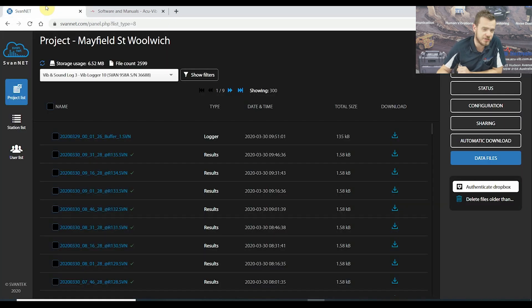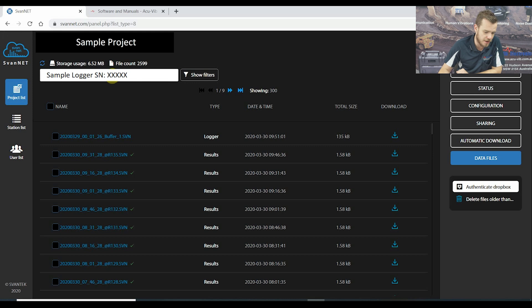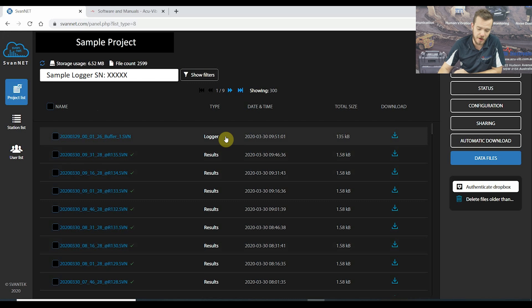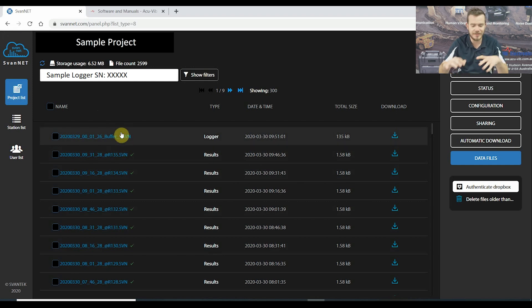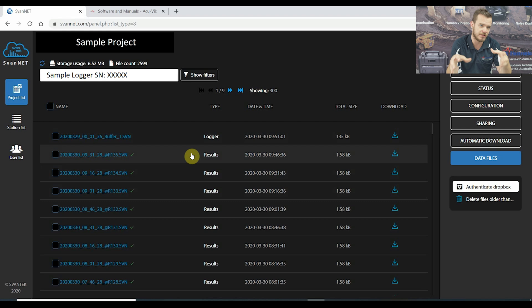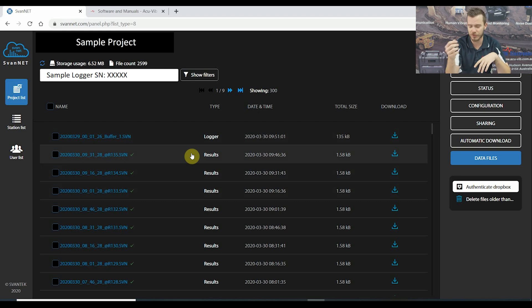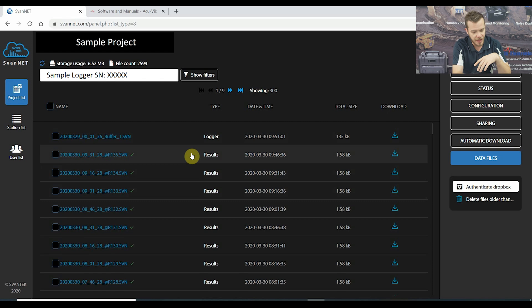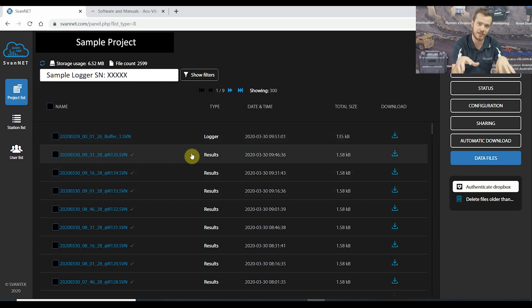After this is done, go back into your project on SvanNet and select the logger you want to download from. You're going to see two different types of files — this is for a Svan 958 sound and vibration logger. You have a logger or buffer file, which is basically time history data — a week's worth based on the logger step you've set. The result file will be one file every 15 minutes, or however long you set the integration time. For a lot of environmental monitoring, 15-minute files for statistical noise is a typical measurement. These result files hold statistical data, while the logger file holds PPV, max, mins, RMS values for vibration, as well as LEQ for sound.